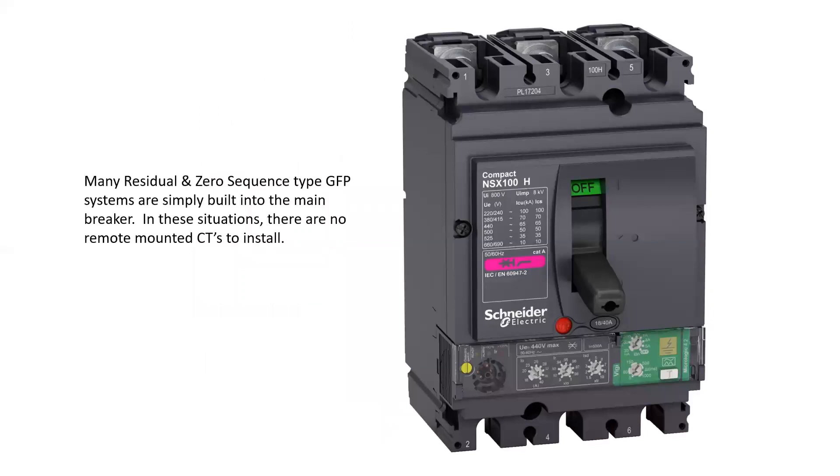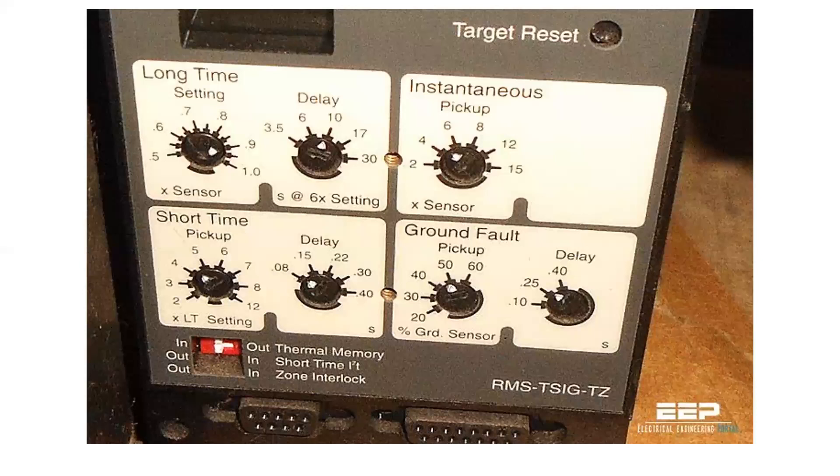So here is a ground fault protection breaker. It has the CTs inside it and it has settings on the bottom. So all of the shunt trip and the relay and the CT is all built into the breaker itself. And so you would be able to set with a dial cam how many amps and for how long that ground fault current is able to flow before the main breaker trips.